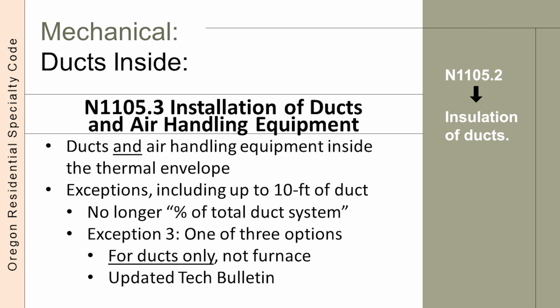There are exceptions for some ductwork to be installed outside of the thermal envelope. And let me emphasize this is just for the ductwork. Any furnace or air handler should be located inside the thermal envelope for a new home.